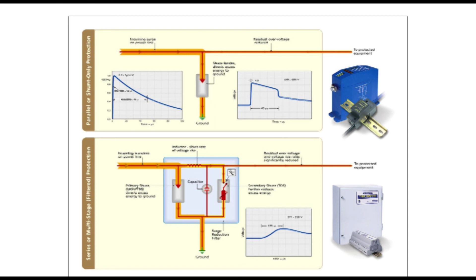There's your single-phase filter. Again, you can see the shunt protection modules at the front end and your LC, so your inductor and capacitor low-pass components, at the back end. Start at about 3 amps and up to 2,000 amps. Okay? You have to rate them by load current. Unlike those earlier photos I showed you, the shunt protection modules, these actually sit in series with your load because you have that series connected inductor. So size them according to your circuit breaker, basically.